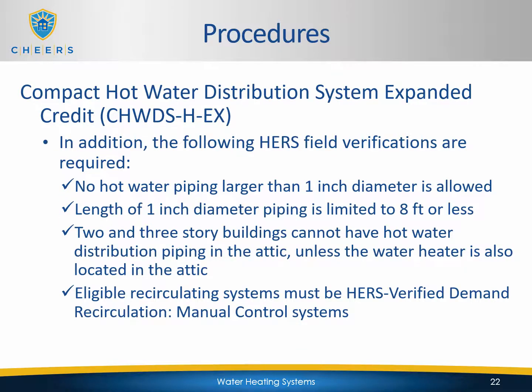So in addition to meeting all the requirements of the basic credit, the following HERS field verifications are required. So you will field verify that no hot water piping larger than 1 inch in diameter is present. Any length of 1 inch diameter piping is limited to 8 feet or less. So you can have 1 inch diameter piping, you just can't have larger than 1 inch. For 2 and 3 story buildings, you cannot have hot water distribution piping in the attic unless the water heater is also located in the attic. And eligible recirculating systems must be HERS verified demand recirculation with a manual control system.